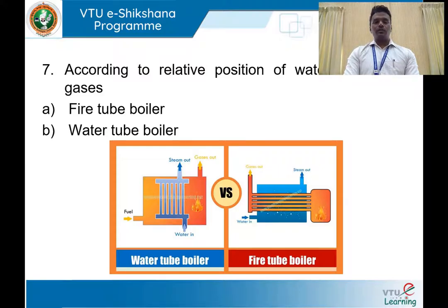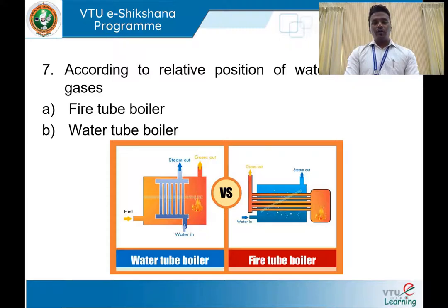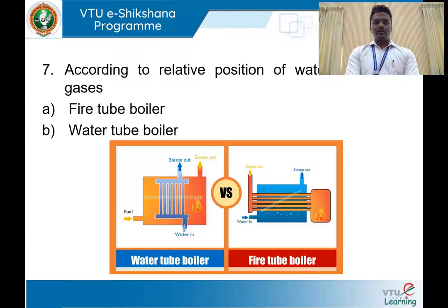The most important classification is based on the relative position of water and hot gases — we have fire tube boilers and water tube boilers. In a fire tube boiler, there are series of tubes placed inside the boiler shell and the hot gases produced from combustion are made to flow through those flue tubes, while water surrounds them. In a water tube boiler, water flows through the tubes and the hot gases pass around those water tubes. The Lancashire boiler is a fire tube boiler, and the Babcock and Wilcox boiler is a water tube boiler.